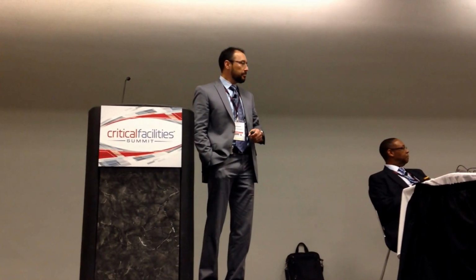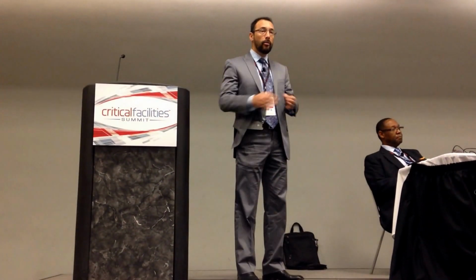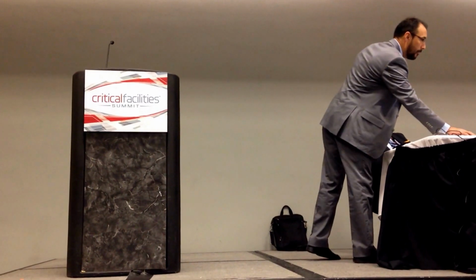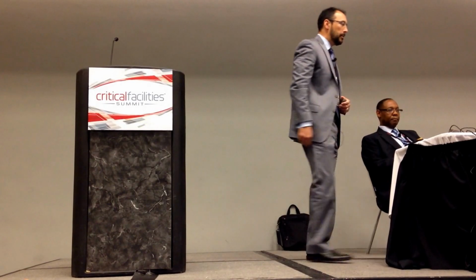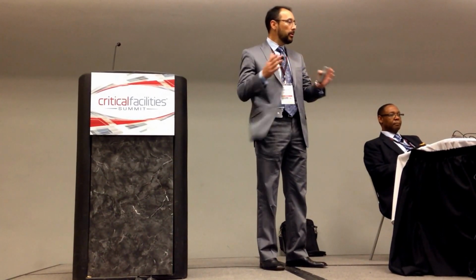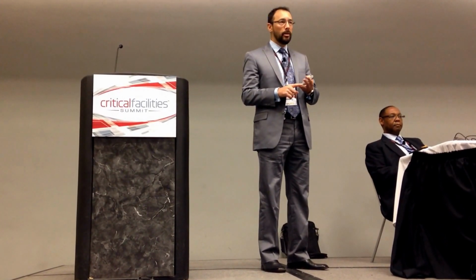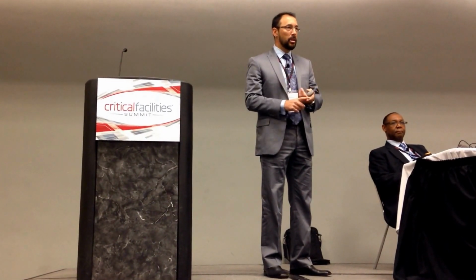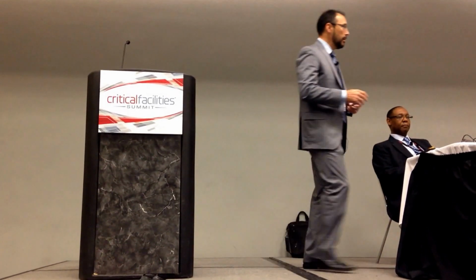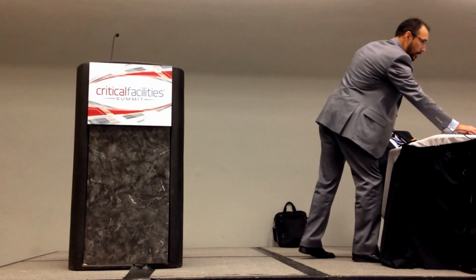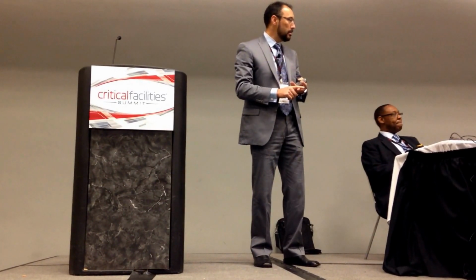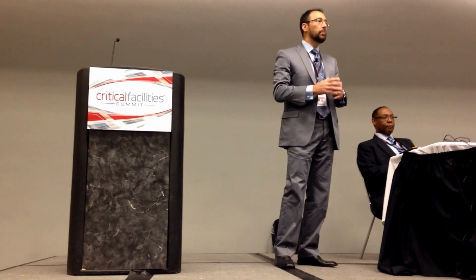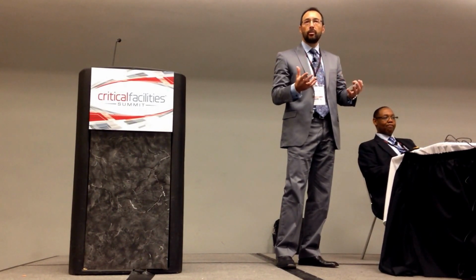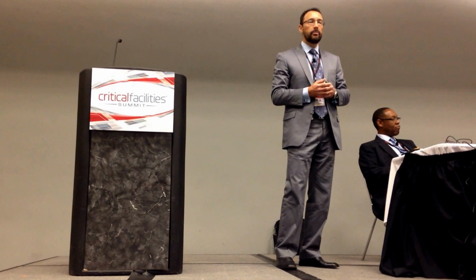This is what happens from a capacity standpoint over the data center's entire lifespan. Originally, there was a plan to fill out the data center in a regular way over time, utilizing space, power, cooling, and networking in an optimized way to reach the capacity goal in the room, whether that's total kilowatts or kilowatts per square foot. Then, in reality, the data center goes into operation, and a whole different set of IT equipment comes in with different operational and physical characteristics. They use the space, power, and cooling resources in a completely different way, and now you're dealing with the impact of a wrong design from day one.